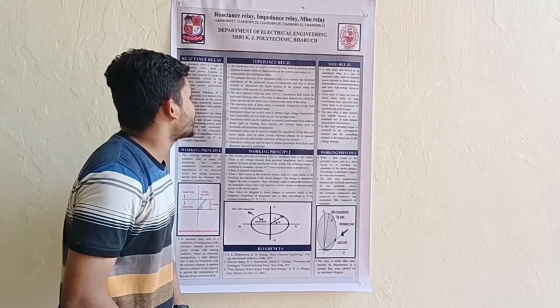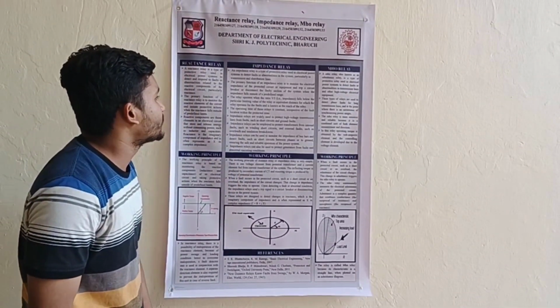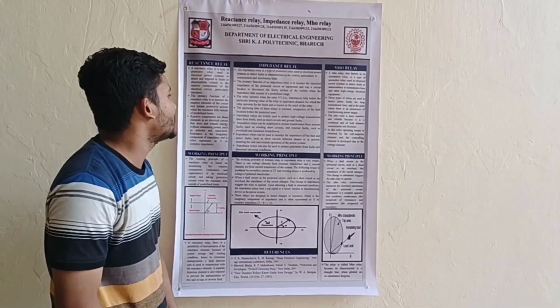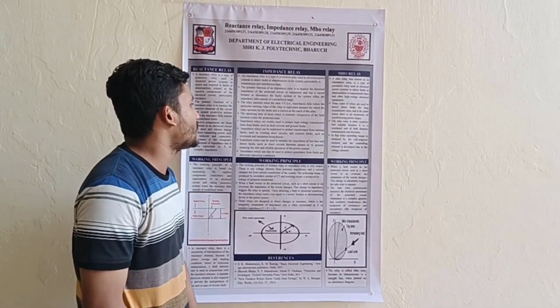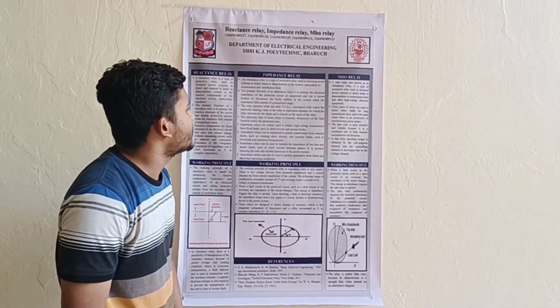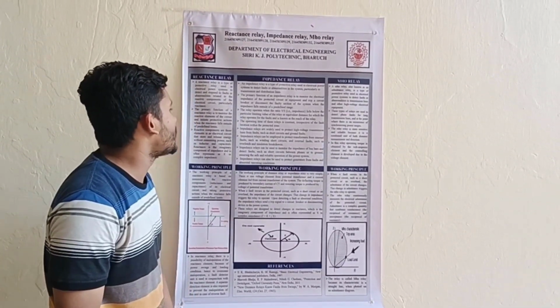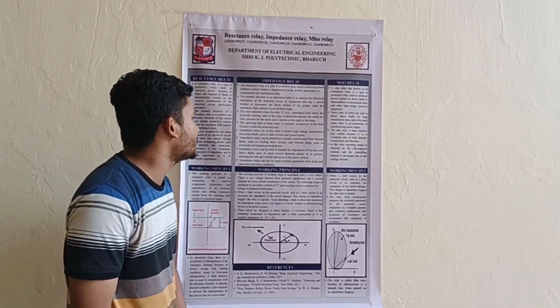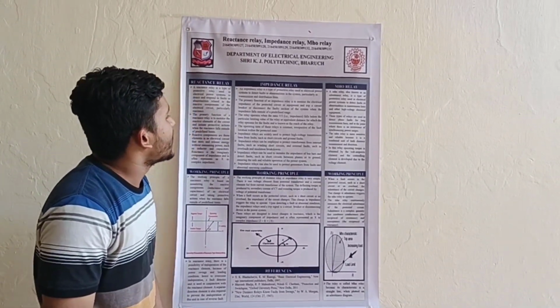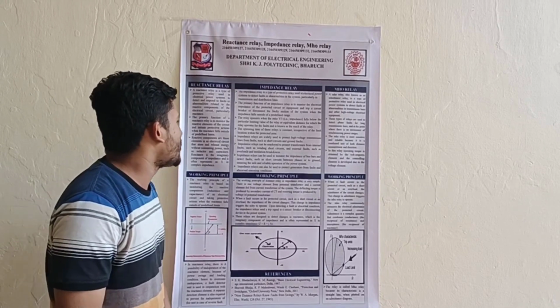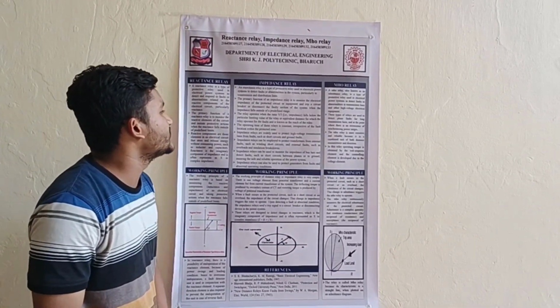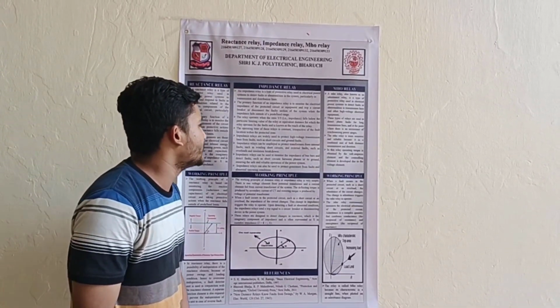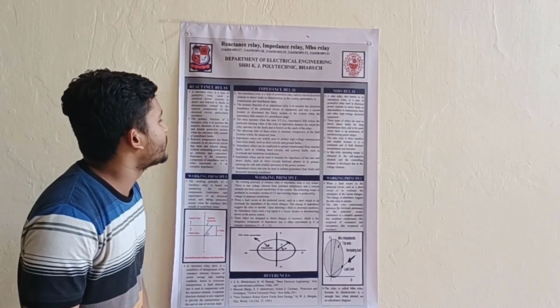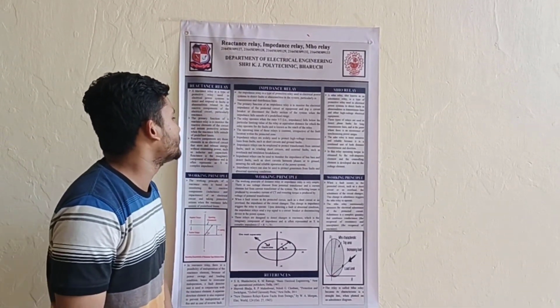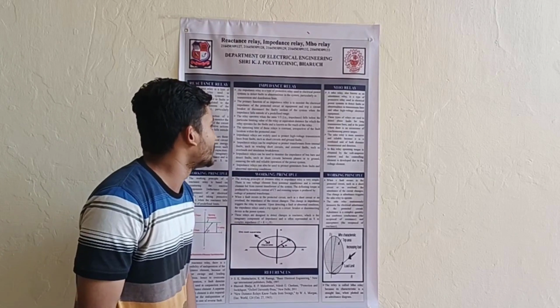The relay operates when the ratio V by I falls below the particular limit value of the relay, or equivalent distance for which the relay operates for the faults, and this is known as the reach of the relay. The operating time of this relay is constant irrespective of the fault location within the protected zone.